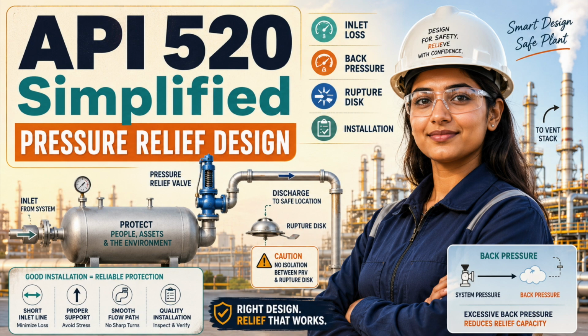Rupture discs create a different set of decisions. They are fast, simple, and have no moving parts, but they are non-reclosing devices. Once a rupture disc opens, the process remains connected to the discharge path until intervention occurs. You therefore need to think beyond burst pressure and consider product loss, shutdown implications, environmental release, flare loading, replacement access, detection, and isolation. A rupture disc is simple hardware. Its application is not simple.